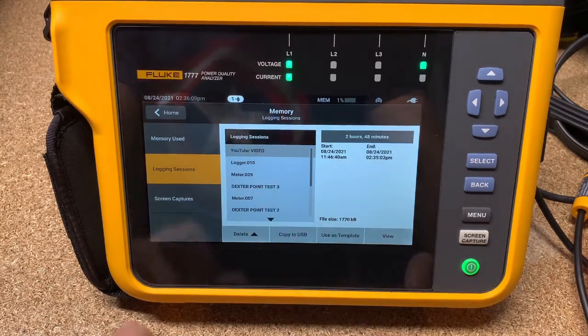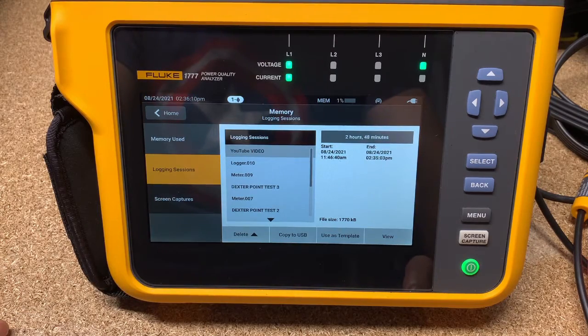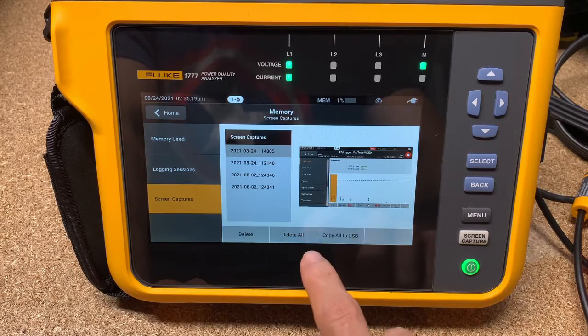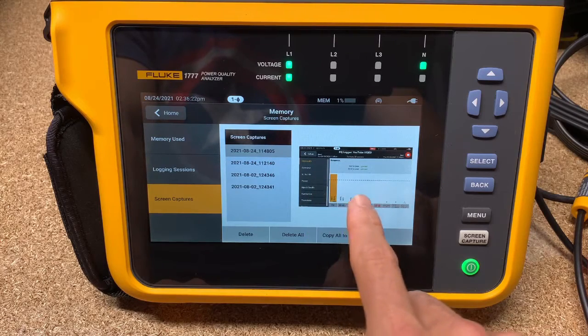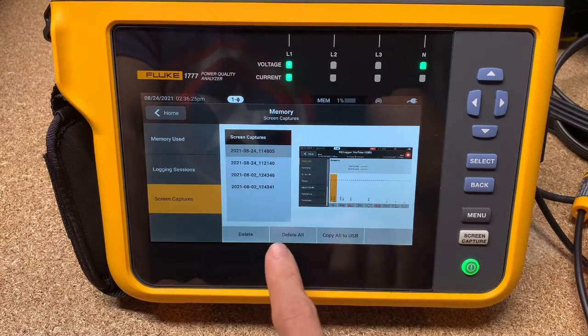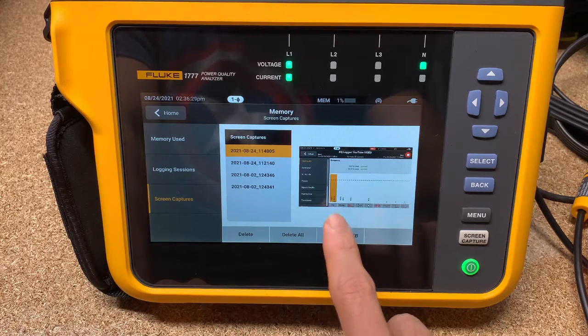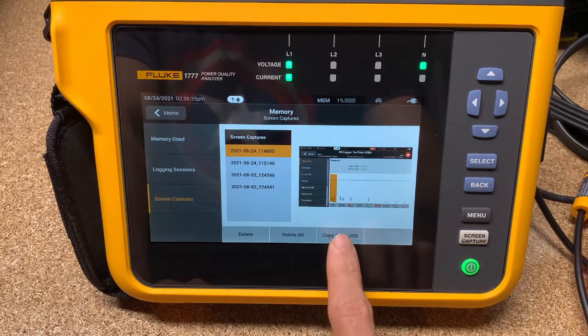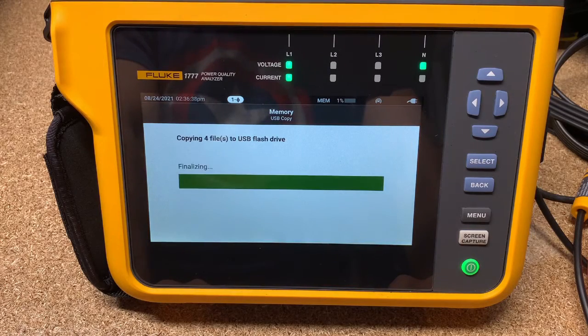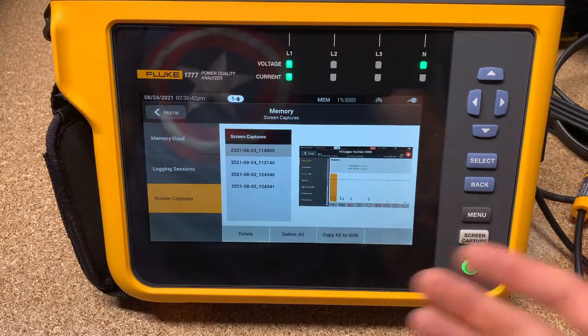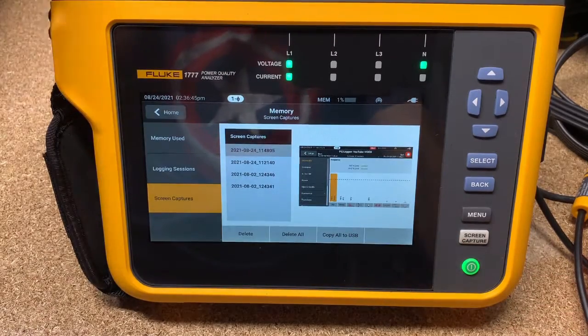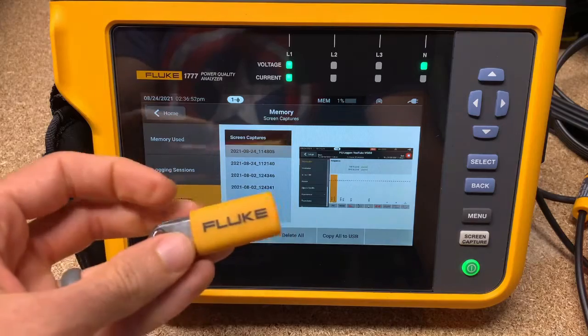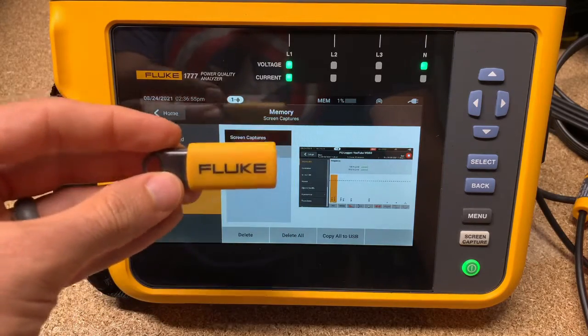If you want to also copy screenshots, you can go over to screenshots and see which ones we got. We got that screenshot earlier — this is the screenshot that didn't have much in the power quality health screen, and we saw more of it this time. So we can click that and say copy all to USB. It copies all four files and now we're done. At this point we can disconnect everything — pull out the USB stick, bring it back to our PC, download the data, and we're off and running.